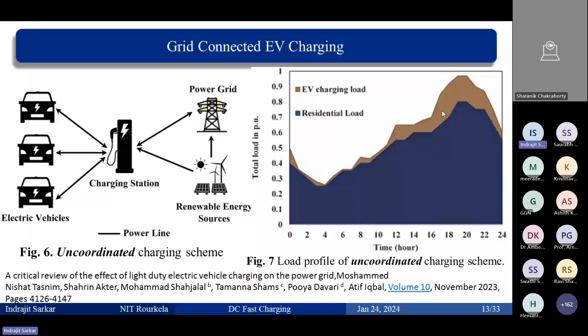If we have multiple EVs, it causes substantial stress on the distribution grid, which is a 400-volt grid. The load curve moves upward and increases the load on the transformer, because the EV adds a delta amount of power that has to be consumed from the grid. That delta amount is not insignificant; it's a significant amount of power. And since the transformer installed in your locality was maybe installed 20 years back, it is already overloaded.